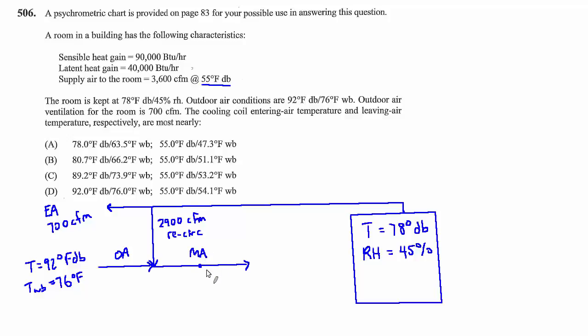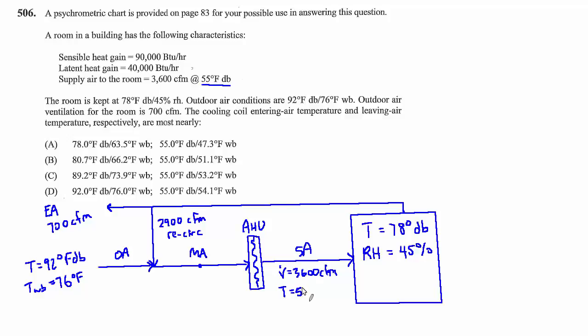Those two streams — recirculated room air and outdoor air — are mixing, giving us a mixed air condition. That mixed air enters the coil at the air handling unit (AHU), and off the coil we have supply air to the room: 3,600 CFM at a known dry bulb of 55 degrees, though the wet bulb is unknown. Since each answer choice has different entering air dry bulb temperatures, the fastest approach is to find the mixed air dry bulb temperature and match it to an answer.